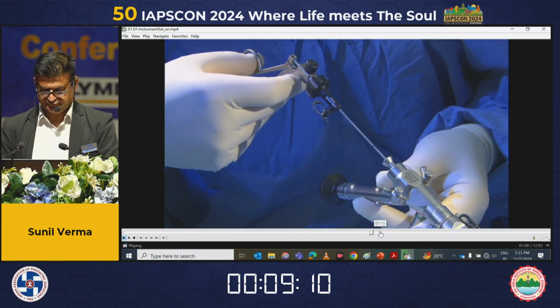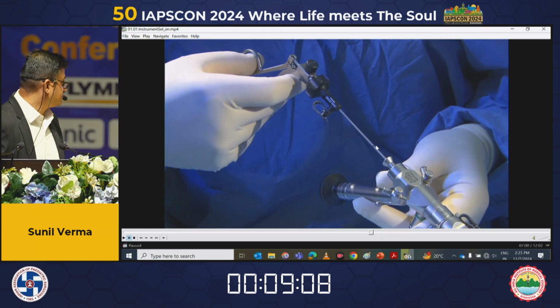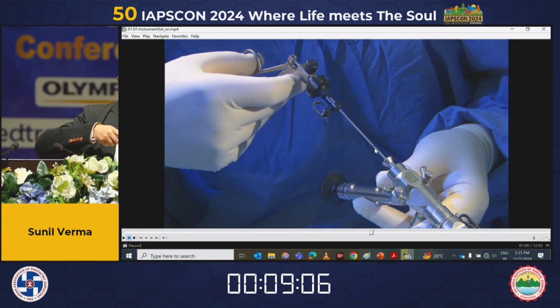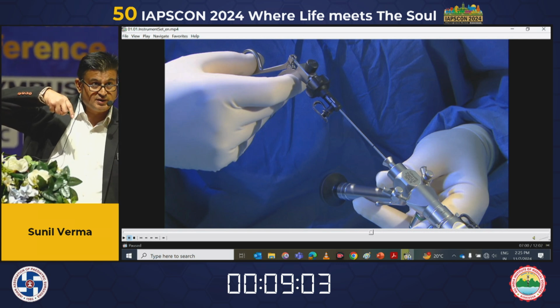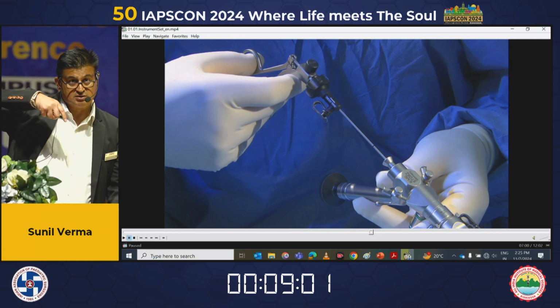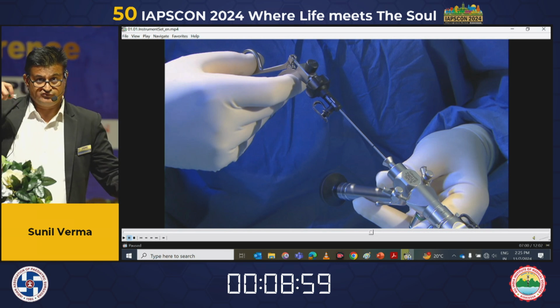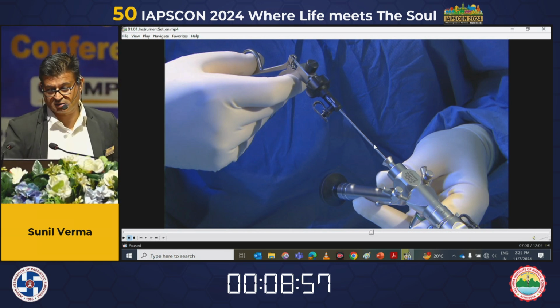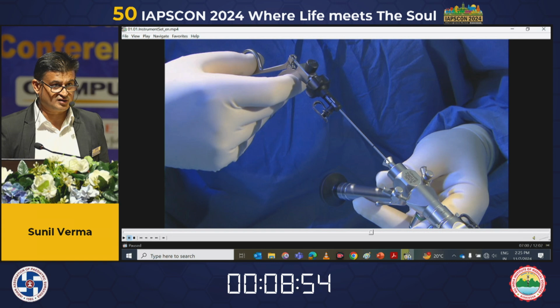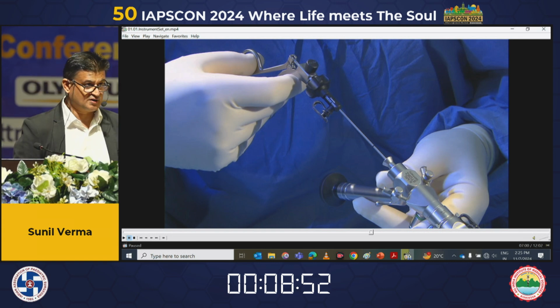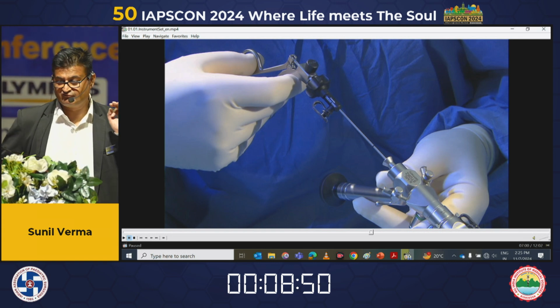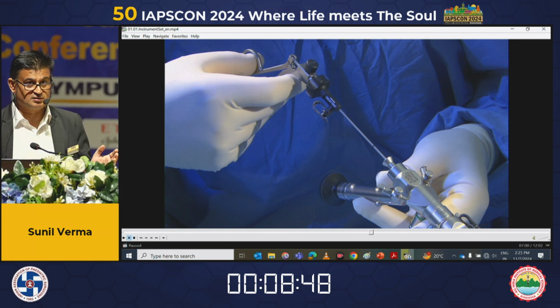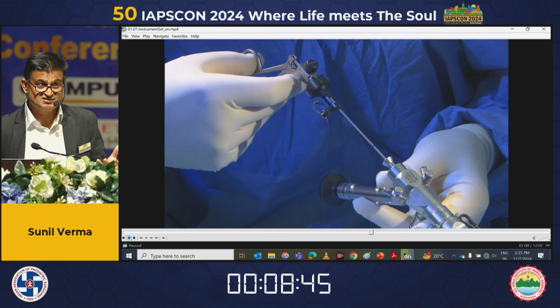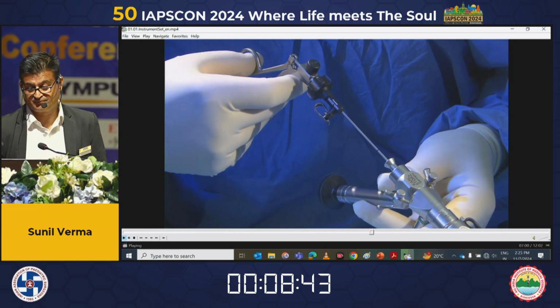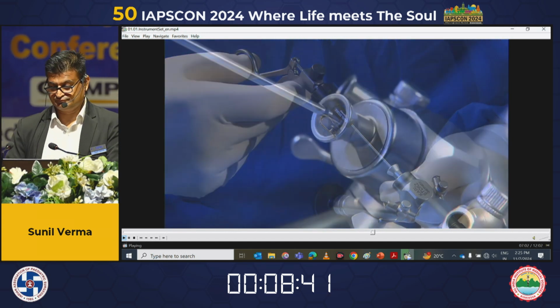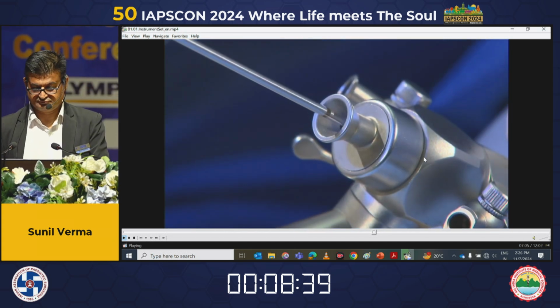So this black marking over here is important, because when you're working with a 30 centimeter long instrument, you are actually waiting for when you are going to reach the lateral ventricle. So you can come very fast. The moment this black mark comes at the tip of the funnel entrance, your instrument has come exactly to the tip. With further advancement, you will be going into the ventricle, because if it's a scissor, it could be a little risky. With the funnel-shaped opening of the working channel, the tip of the instrument is perfectly aligned with the tip of the endoscope.